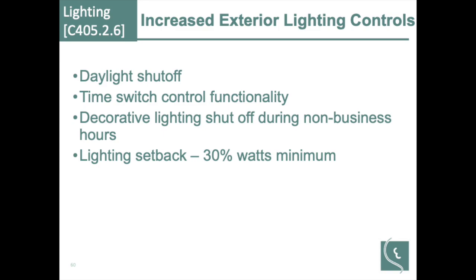So back to that last slide, you have to have a high-low on your exterior lights. You are required to have daylight shut off and time switch control. The 30% setback can be either dimming, or it can be selected fixtures. So you could say, okay, I've got a larger parking lot out in front of the building. The ones further away, I'm going to go ahead and turn off. And the ones closer in, I'm going to leave on all the time. And they do call out when this specifically has to happen.